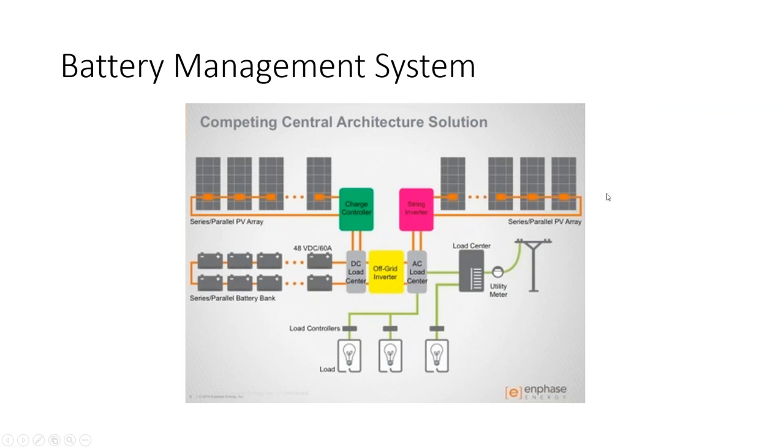All right, so kind of getting back into yesterday's discussion, when you design battery solar arrays, one thing to keep in mind is they're a lot more flexible than what you think. I found that a certain manufacturer might say that their system is not compatible with others, and really what they want you to do is stay within their product line. But when you talk with, say, the battery inverter manufacturers, they often say, oh yeah, you can just AC couple our battery inverters right next to an existing solar array. It's generally the solar companies that want you to use their battery inverter alongside their existing system.